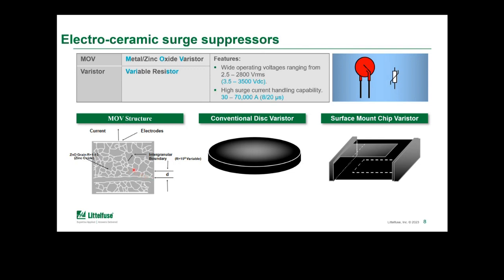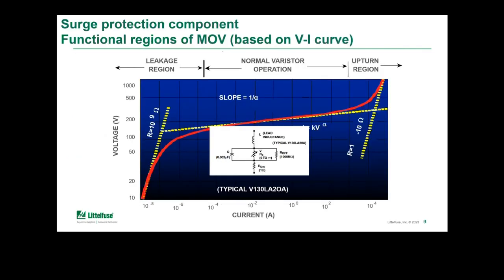And in the parallel form, that's really what dictates how much current it can conduct during a transient event. So the more parallel paths there are, or the wider the disk, the more energy it can handle. And this is a typical VI characteristic curve of an MOV, and this is its equivalent circuit model. Basically, in the leakage region, we're in a linear or ohmic state where we have a very small amount of current being conducted over a change in voltage. So the Rx value is typically ignored because R off is going to be the predominant resistance characteristic. In normal varistor operation mode, this is when we enter the nonlinear or clamping portion of the curve.